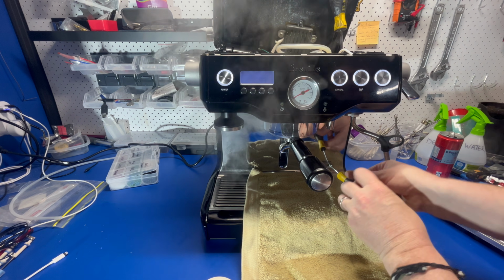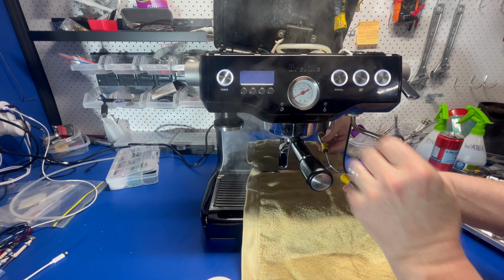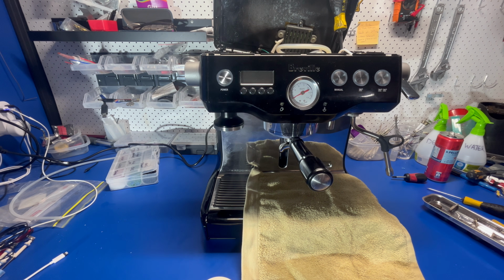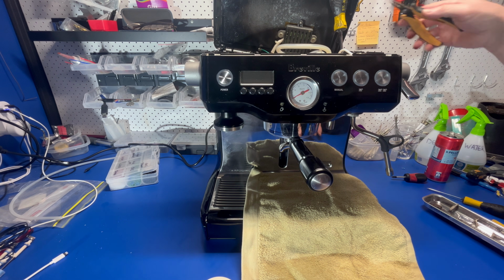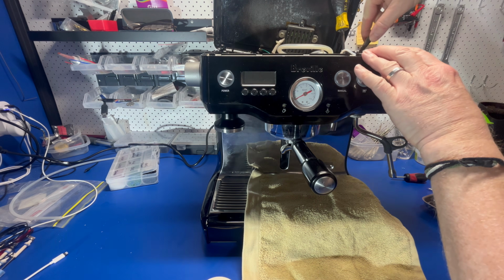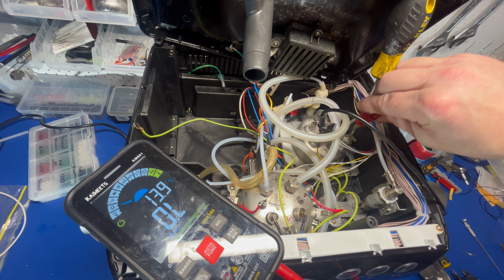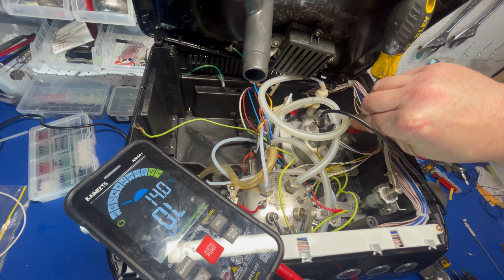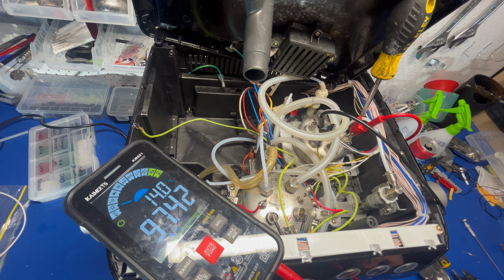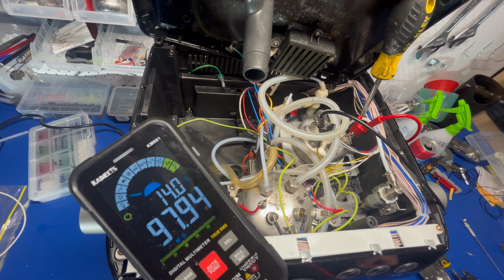But the best way, if you're confident enough, is to shut down the machine after the draining part, take the lid off and disconnect the red wire to the probe, then measure the resistance with a meter. This machine has just had brand new probes installed, and you can see that it's measuring about 100 megaohms.